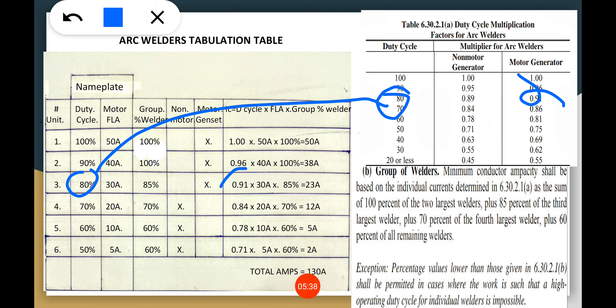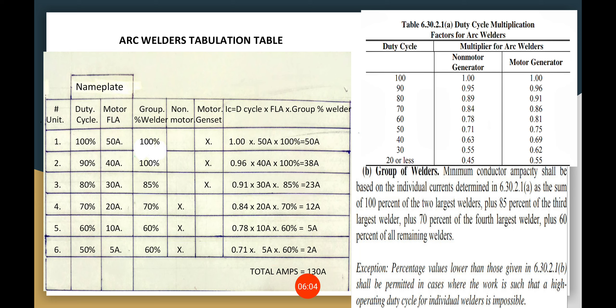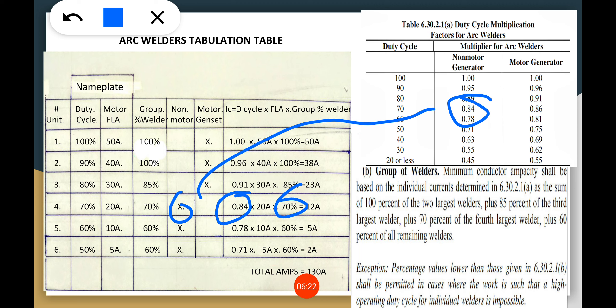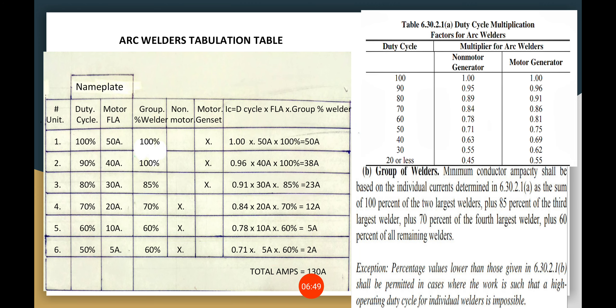For the fourth unit: the duty cycle is 70%, and since this is a non-motor generator we get 0.84 from the table — not 0.86. So 0.84 times 20 amperes times 70% group welder factor = approximately 12 amperes. The fifth and sixth units get a 60% group welder multiplication, based on the non-motor generator table values. When we sum all of these up, we get a total of 130 amperes for the group of welders.